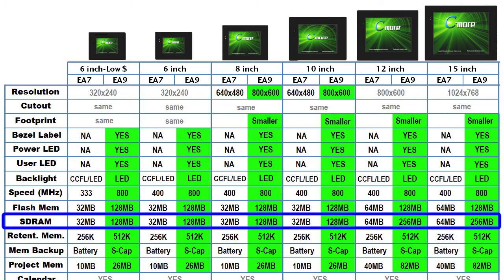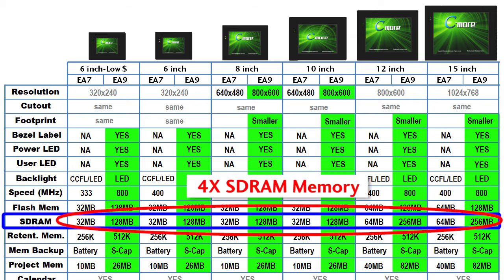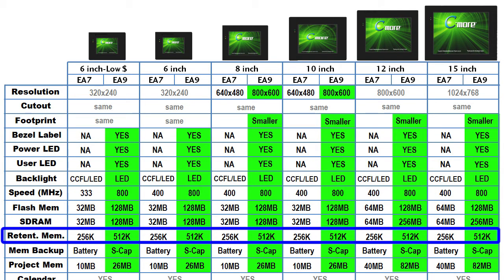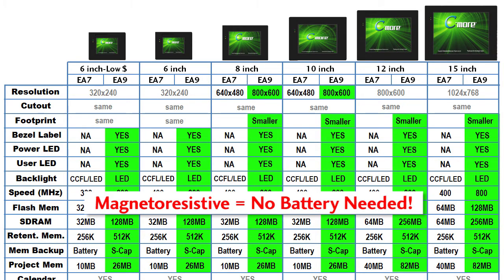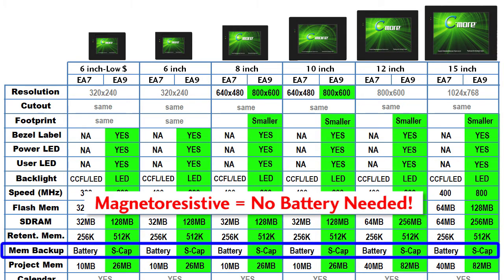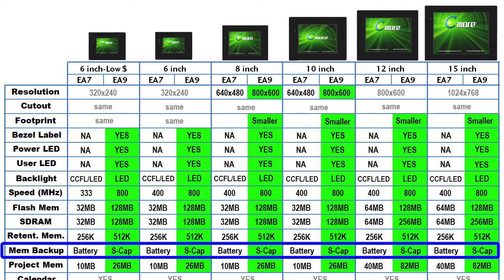All of the SD RAM has been quadrupled across the board and the retentive memory has been doubled on all panels. And the retentive memory is now magnetoresistive, so you don't need a battery to keep retentive data and that's one less thing you don't have to worry about replacing in the future.